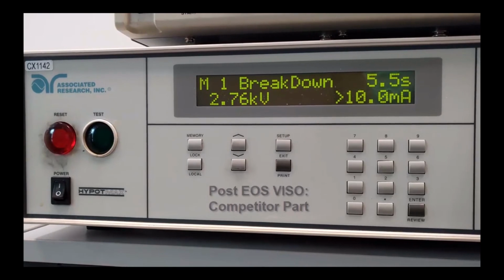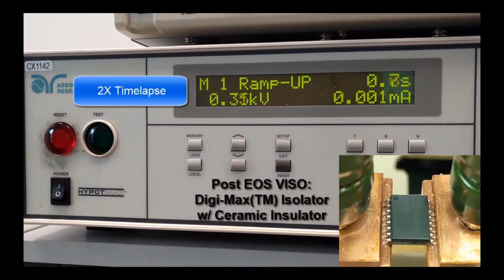Now we test the Digi-Max isolator, which is still passing 5,000 volts after 60 seconds, even after it had been damaged by electrical overstress. This experiment shows that the isolation performance of the Digi-Max isolator remains intact even after the EOS event, while the competitor part has degraded.